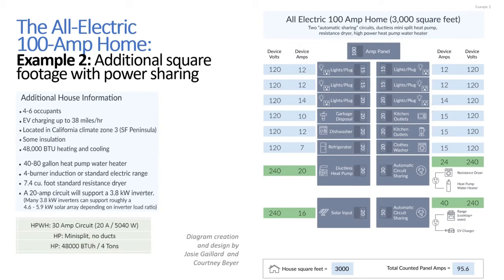Jeff wrote that for domestic hot water, the retrofit-ready 120 volt heat pump water heaters becoming available, it looks like in April from Rheem and others, are estimating up to a 700 watt draw. Go ahead and correct me in the chat if I misspoke, Jeff. Right, and where I showed it in my chart, I was counting around 360 after coincidence, because that horizontal chart was all about counted panel watts. So I was accounting for roughly 700 to 900 watts on the 120 volt water heaters.